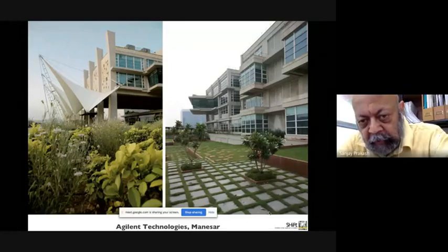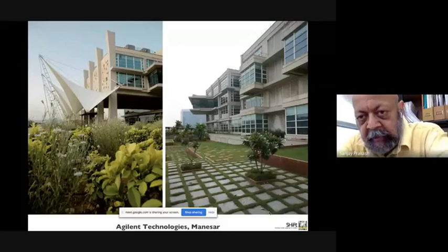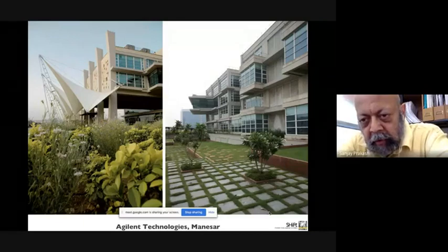That is to say, a false floor, which is expensive in its own right, a false floor where you could feed cool air, and that would just settle in the bottom 6, 8 feet, whatever, and so on. It's called displacement ventilation, technically speaking. And then we vented out from the top.